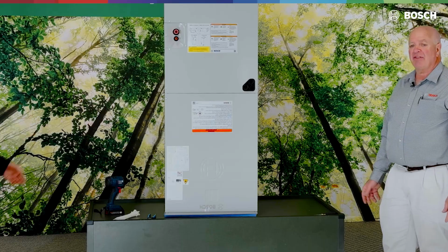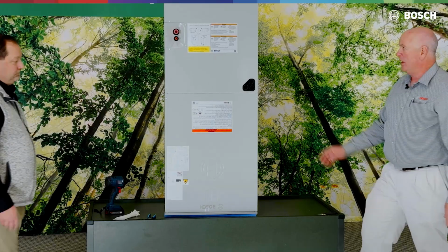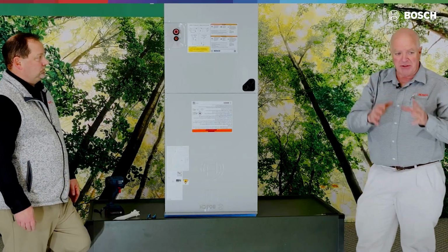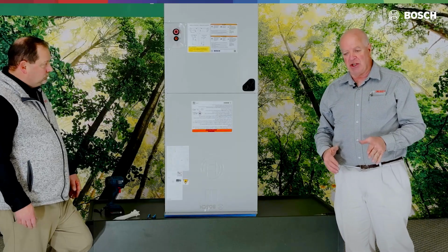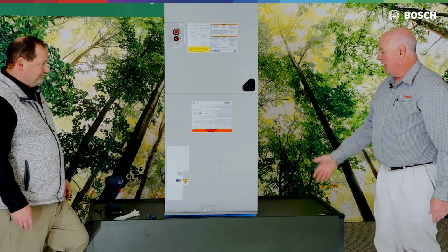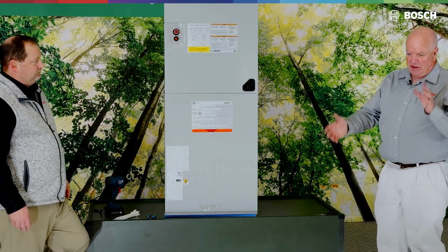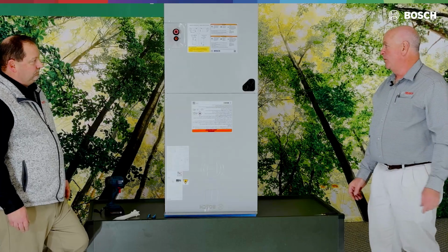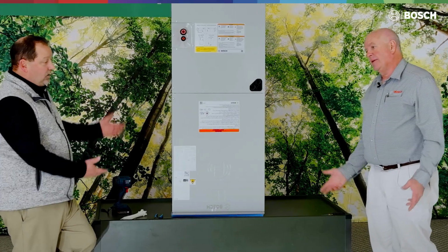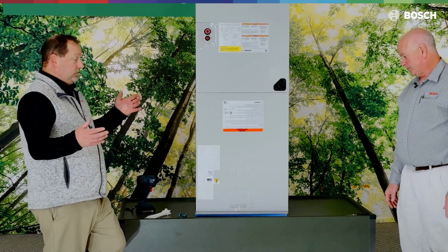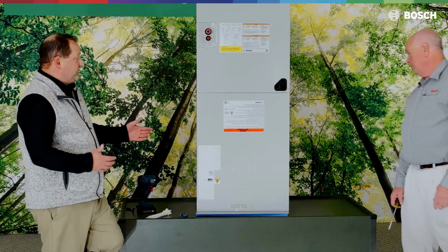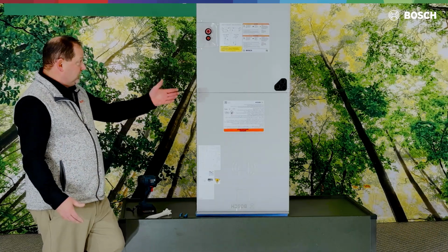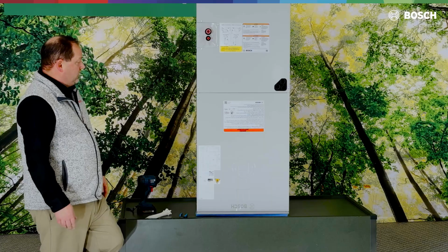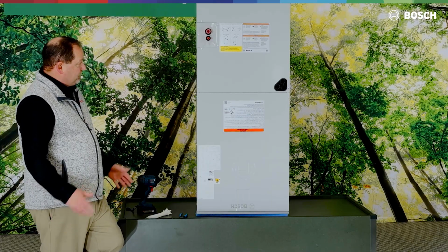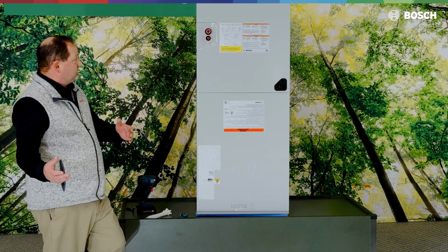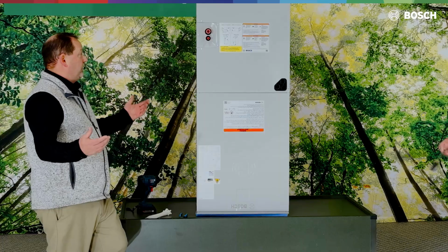We like the idea of canvas collars on our ductwork between the units. The canvas collars are not for alignment purposes, but for sound attenuation. We're going to put a canvas collar on the bottom and on the top to keep that sound from carrying out through our unit. So now we're ready to install it. Now that we've done the field conversion of the air handler into downflow, we're able to connect it to the canvas collar, connect it to the supply air plenum, and finish the connections: refrigerant lines, get the outdoor unit set, run some lines, and be able to weld it all up.